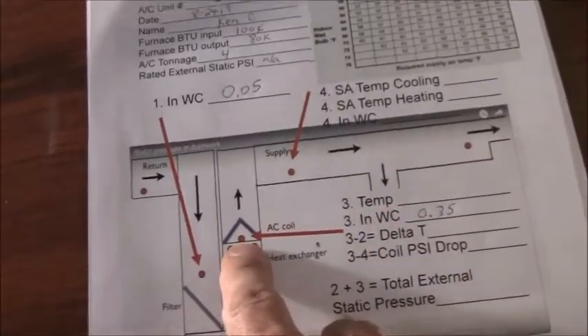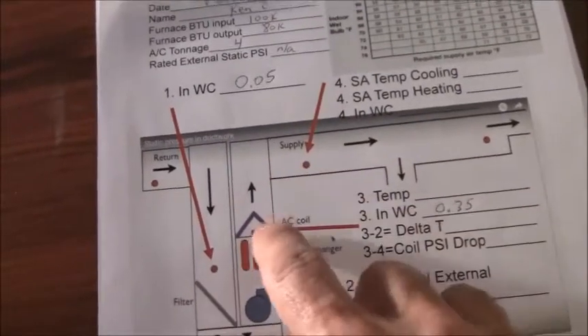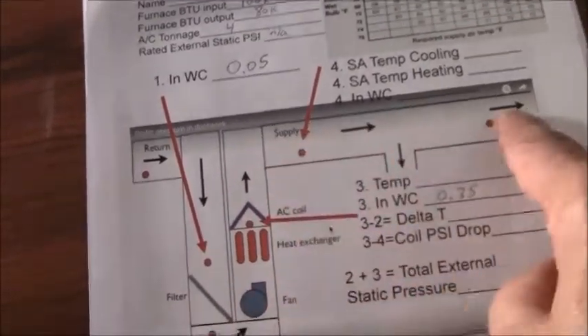Now we need another number. This number right here after the coil where it goes into the plenum. Now, here's the coil. This sample point here is before the coil. I took out a screw right there, and that is where we're going to go after the coil, and it goes into the plenum. Okay? It could be anywhere up there, but since there was a screw right there, it was just easy for me to remove that screw and use that as my sampling point.